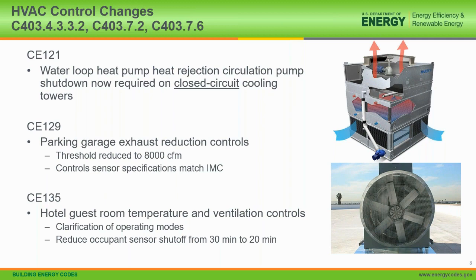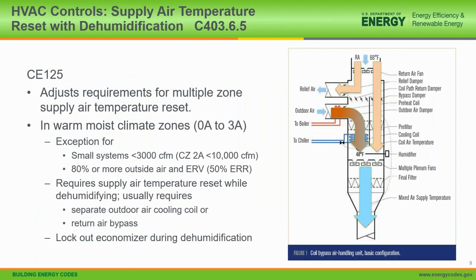CE 135 relates to hotel guest room temperature and ventilation controls. Those requirements were added the last cycle. This pretty much clarifies them primarily. There's not really a change in requirements, just understanding that there are 3 different operating modes: one mode for occupied, one mode for unoccupied for a rented room, and one mode for an unrented room, and how those requirements work. There is a minor shift in the requirements where the shutoff was 30 minutes before, now it's 20 minutes, to align better with the lighting shutoff controls as well.